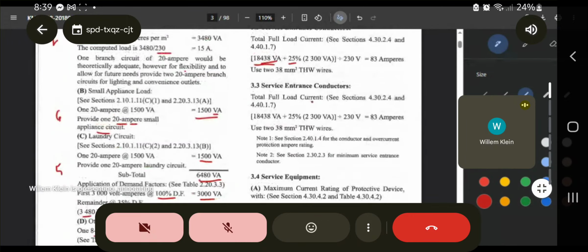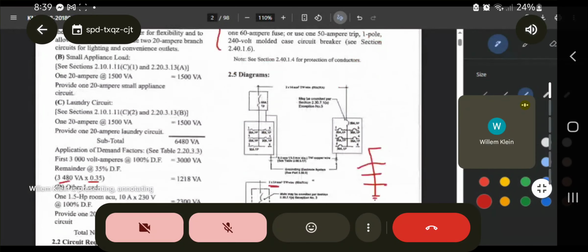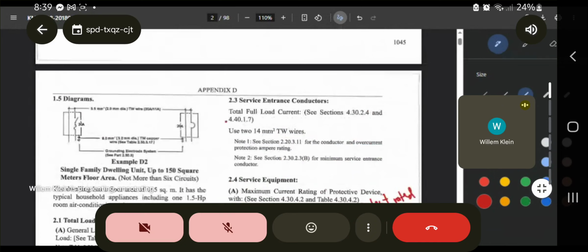So that's why on your highest rated motor, for your full load current, for your conductor. So by the way, we're computing for the conductors nga pala. So this is a different computation from the service equipment, no, the fuse and the circuit breaker. Diba earlier, for the service conductors, we did not actually compute, no. So you just use 14 millimeter square TW wires because that's still within the standard, no, for not more than 6 circuits of single family dwelling unit. So that's why you use directly 14 millimeter square TW wires.